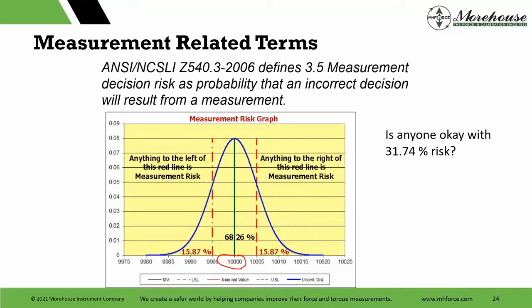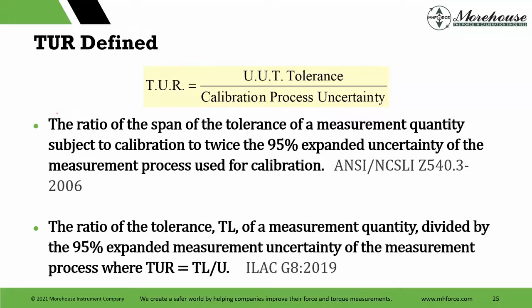Why is that? Well, if we go into the definition of TUR, it is defined in two documents, ANSI Z540.3 and ILAC G8. It's also mentioned in JCGM 106, but not defined. So here we go. I like the ANSI Z540.3 definition. It's more complete. It's the ratio of the span of tolerance of the measurement quantity subject to the calibration to twice the 95% expanded uncertainty of the measurement process used for calibration. The reason I like the NCSLI definition better is because if the tolerance is not symmetrical, the ANSI NCSLI definition is much clearer. The other one doesn't really tell you as much with tolerances that are not symmetrical. So I prefer their definition.